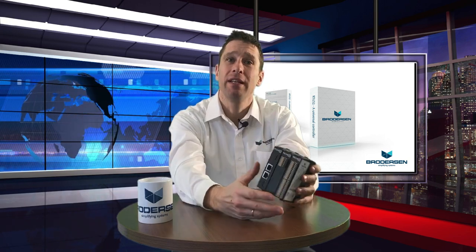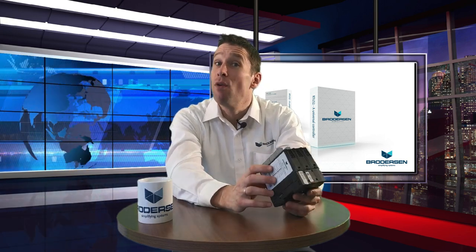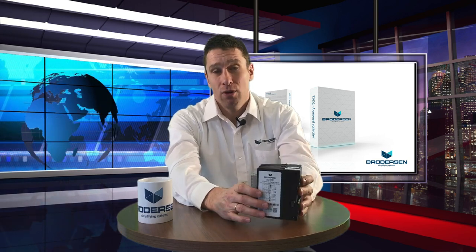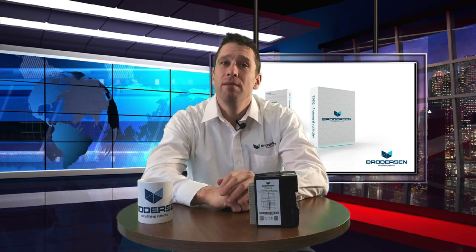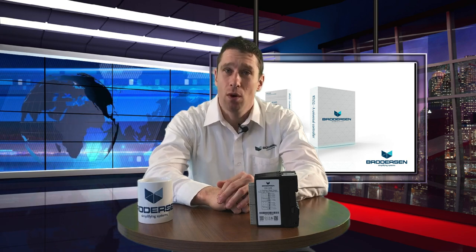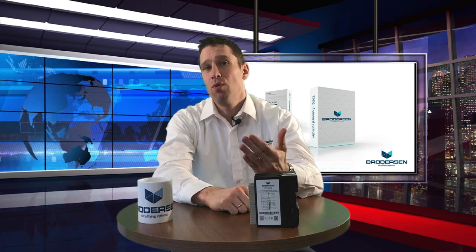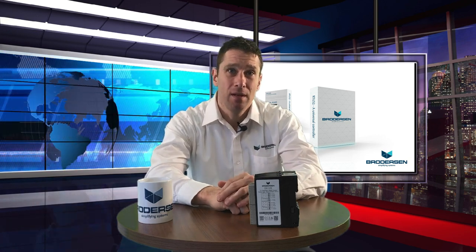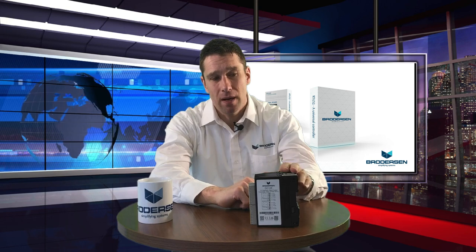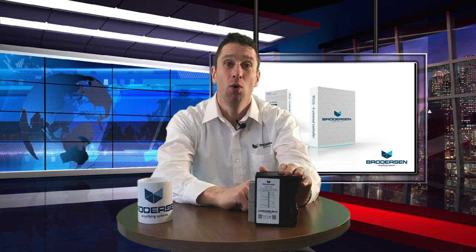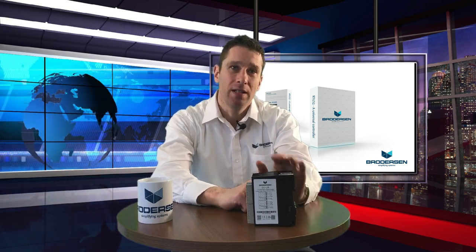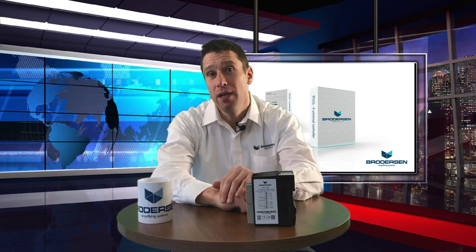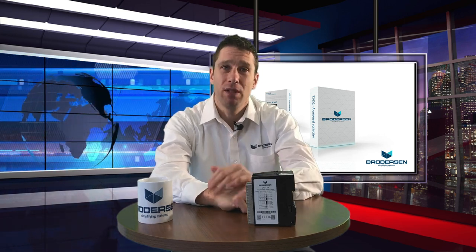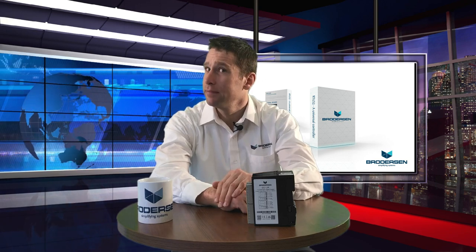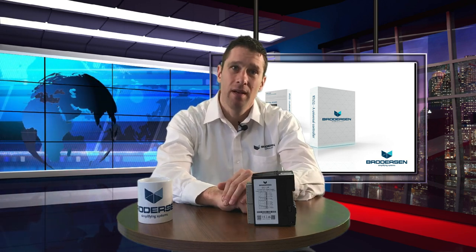Let me give an example of what you could use it for. An example could be you have 4 different machines and you want to be able to run them and program them without stopping them all at the same time. So now, with a quad-core PLC engine, a multi-programmable area, you can actually program machine number 3 with new stuff without stopping machines 4, 2 and 1. So that's the plus side of it.